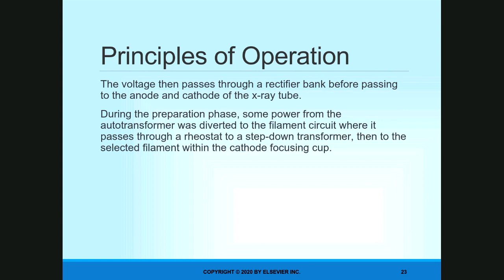Okay, but what happens is the voltage is passing from the negative cathode to the positive anode. And what that creates, because they're opposite charges, is a huge potential difference between the two, meaning that when you're pressing that switch and the X-rays are ready to be released, the cathode is extremely negative and the anode is extremely positive.